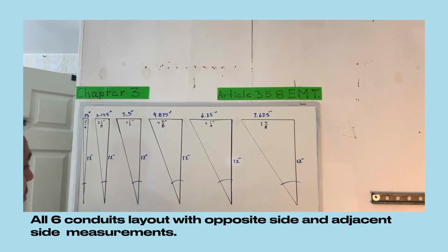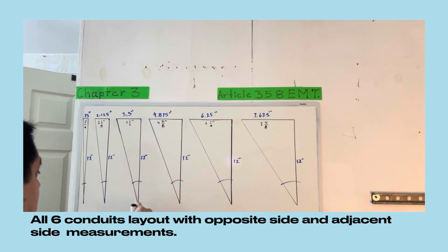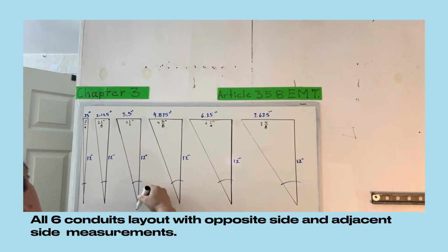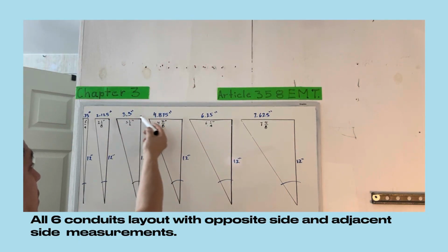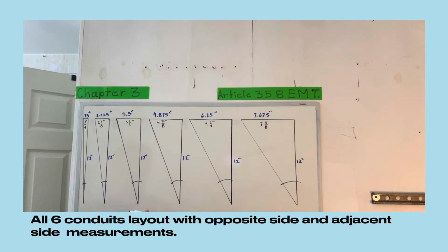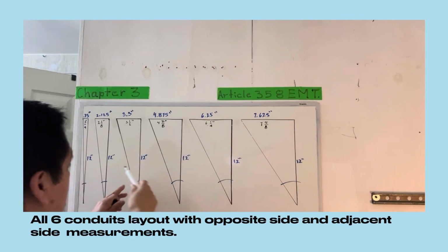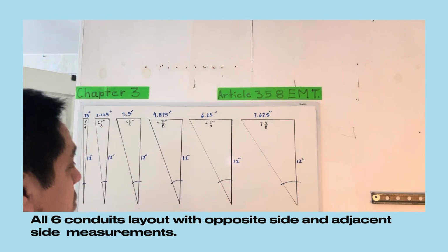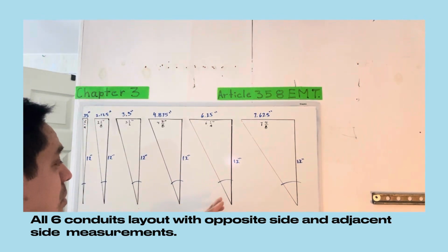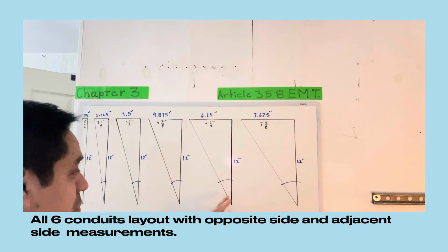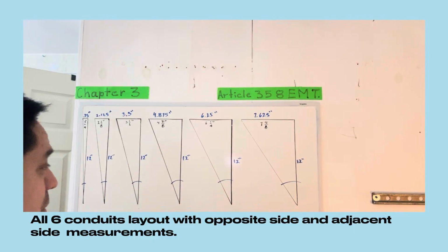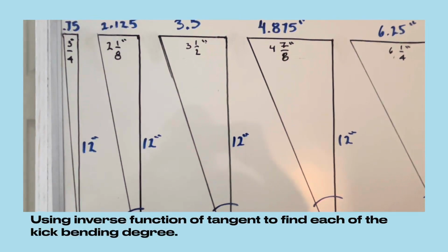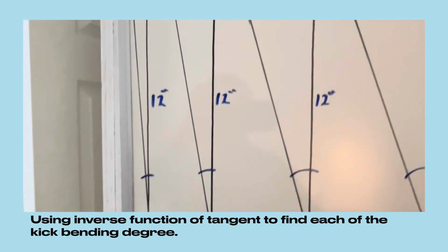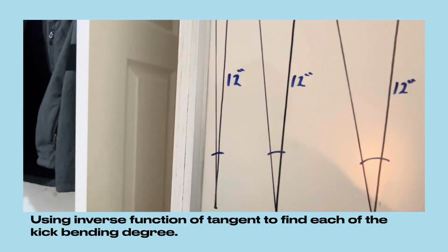The angle we're looking for is this right here, down here. So the opposite to our angle is these measurements up here, and the adjacent side to the angle will be 12 inches. All 6 is 12 inches. So what I need now is to find the degree to bend each of them. What I'm going to start doing is finding the degree of the first kick.